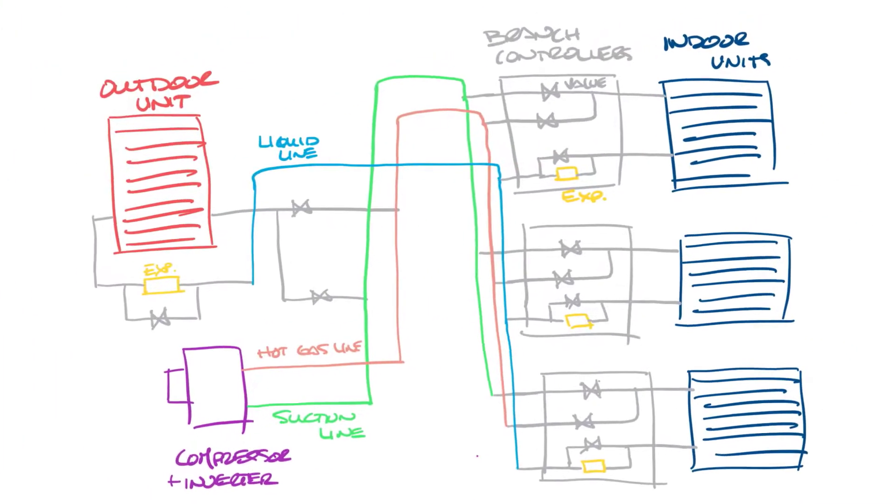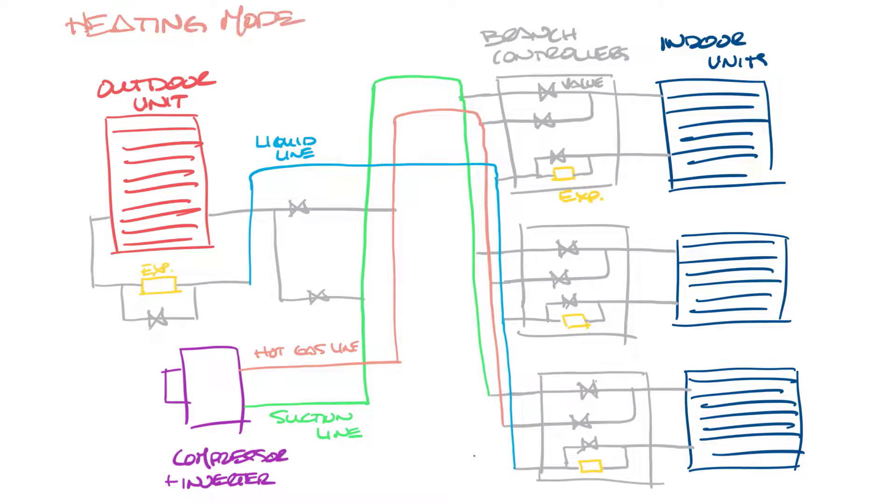Now let's look at what happens during heating mode. Starting again at the compressor, the hot gas comes out of the compressor and through the hot gas line. Now because we're in heating mode we want to send this to the indoor units. So it'll come in and go into each of the indoor units. Air flow will pass through it and send heat into the spaces. Now the refrigerant comes out and goes through the expansion device in each of the branch controllers which will cool it down and connects it back to the liquid line.